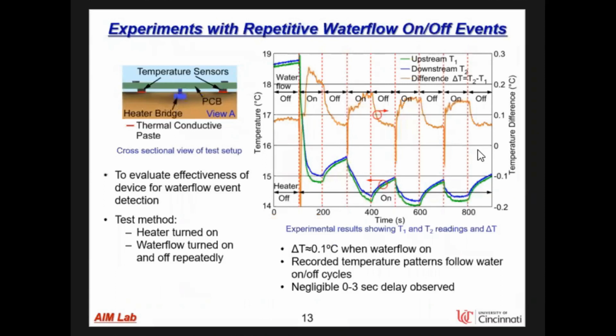The assembled device was deployed for water flow event detection using the setup shown here. The heater was turned on and the water flow was turned on and off repeatedly to emulate water usage events at a fixture. This figure shows the recorded T1 and T2 temperature readings in blue and green, and the calculated delta T in brown curve. These curves show clear pattern in following the water on-off cycles and successfully verifies the principle and functions of the calorimetric sensor, indicating effective device operation. A negligible delay of up to 3 seconds was observed and is not expected to affect this target application.